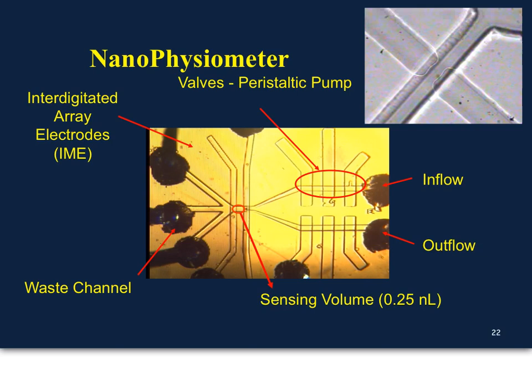And so they also have these interdigitated array electrodes that they put adjacent to it, that could then do electrochemical type detection of analytes depending on each electrode's coating. So they could do both amperometric and potentiometric recordings of things like oxygen uptake and acidification.